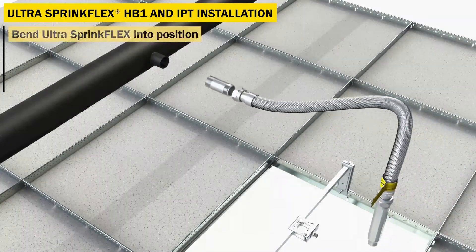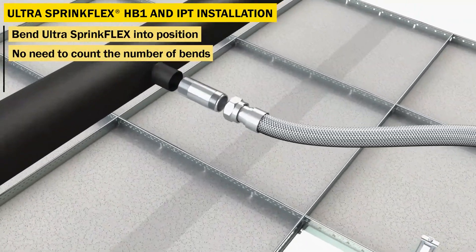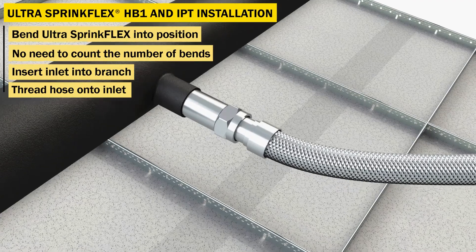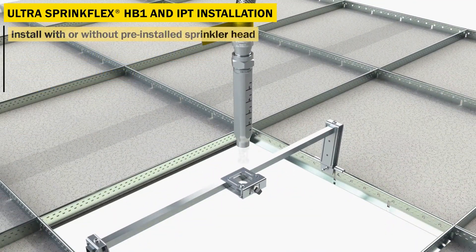Bend the Ultra SprinkFLEX into the final position — do not worry about the number of bends or bend radius. Insert the inlet into the branch and thread the hose onto the inlet. The IPT bracket open hub allows you to install an Ultra SprinkFLEX with a pre-installed sprinkler head.